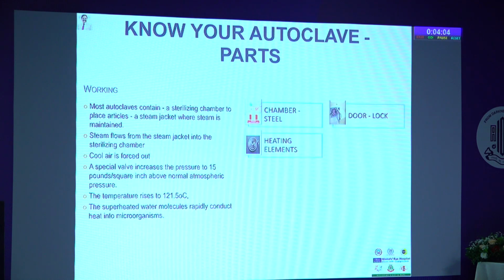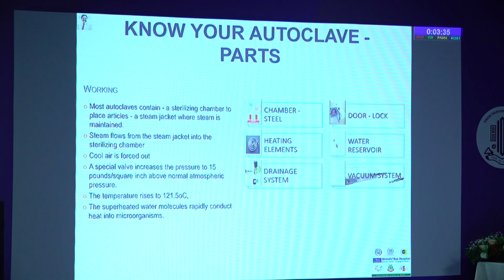And you need to have a look at the heating element also. This is one element you will be changing whenever you are having a problem with heating or when the autoclave fails. And you also need to have a water reservoir. This is very, very important. A good quality water reservoir is important to maintain the temperature and pressure. You also have to look at the drainage system. The same water should not be there. You have to change the water for good quality steam. And for the vacuum-based autoclave, you need to have a good vacuum system also.